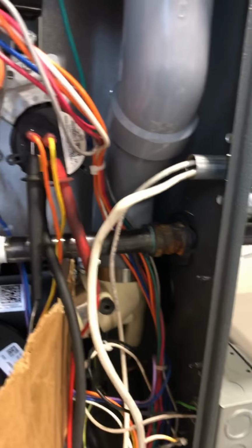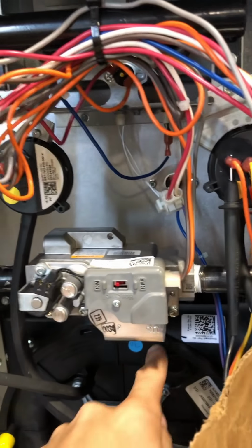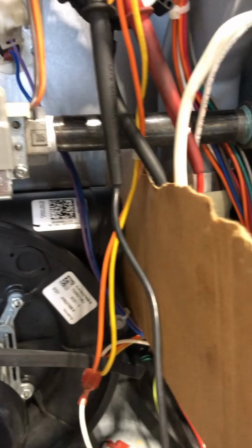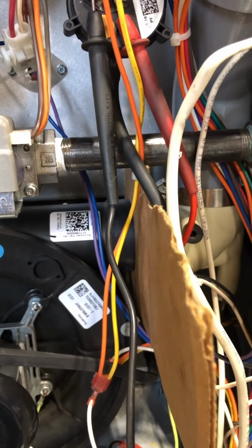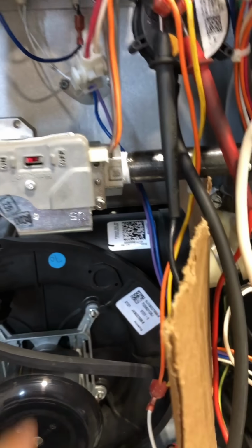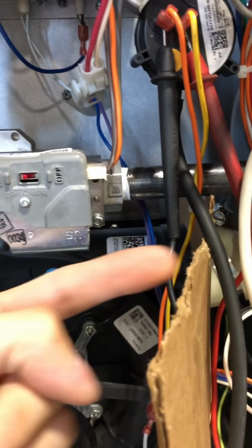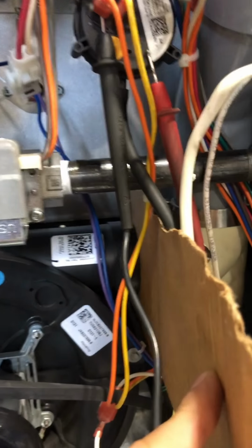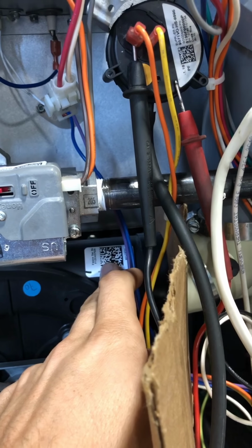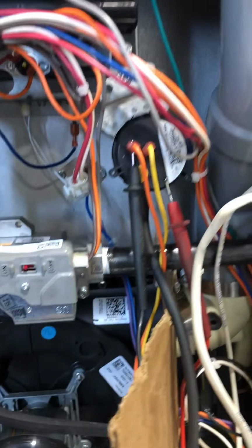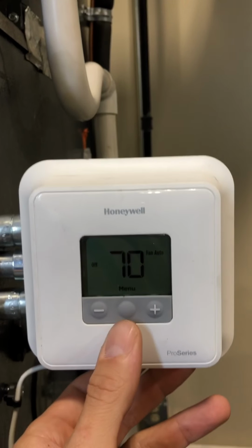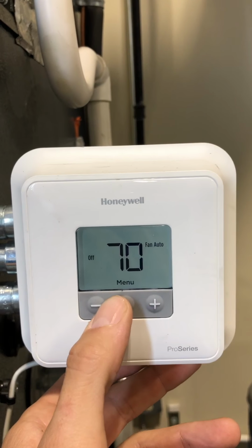So what I've done here is I've actually separated the exhaust pipe from the inducer motor, and I've stuck a piece of cardboard in between there. So basically what happens is this inducer is going to start up, but nothing's going to be able to leave. I'm simulating that there's a blockage in this inducer housing. Okay, and we're going to see what happens. So I'm going to do step number one. I'm going to come over here and give us a call for heat.